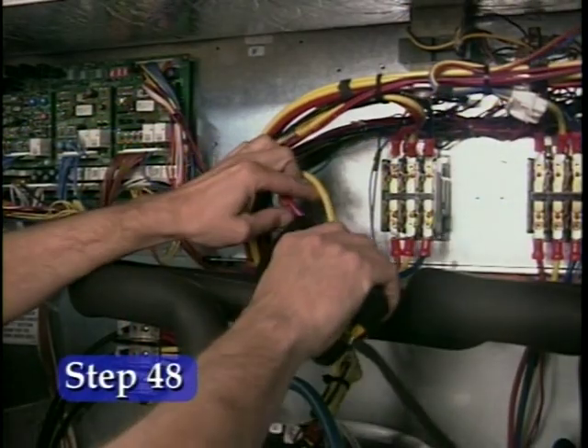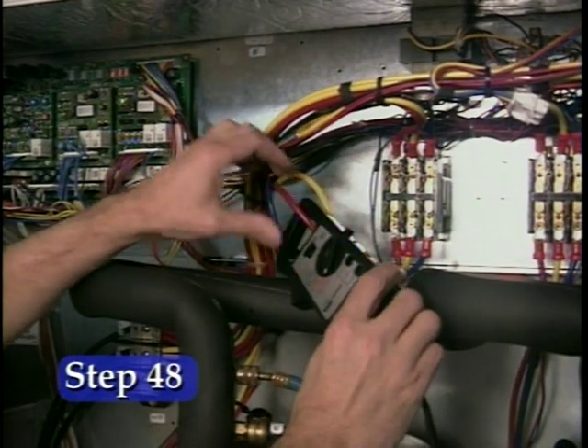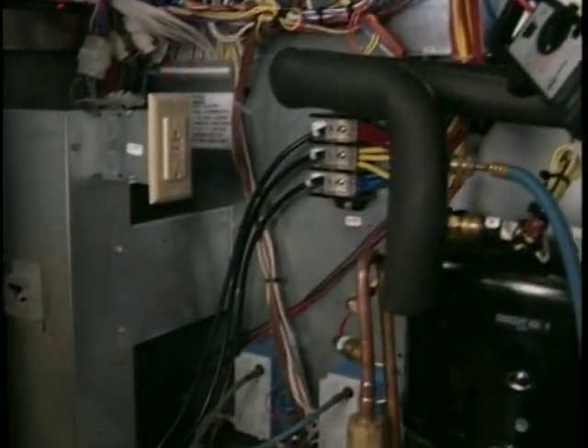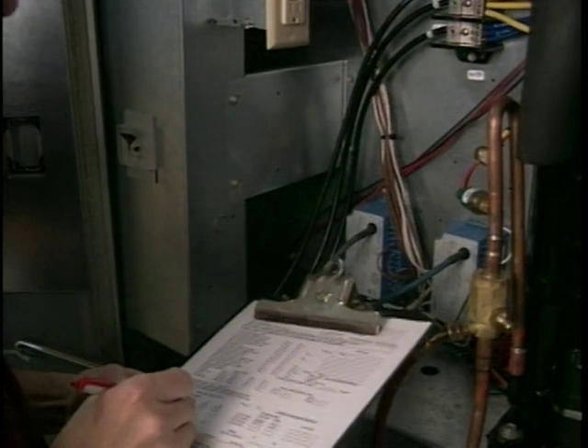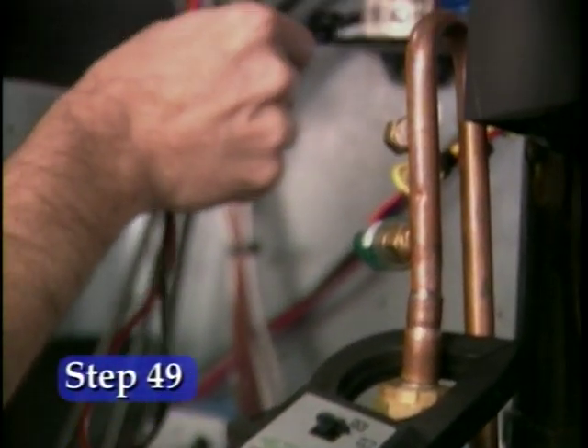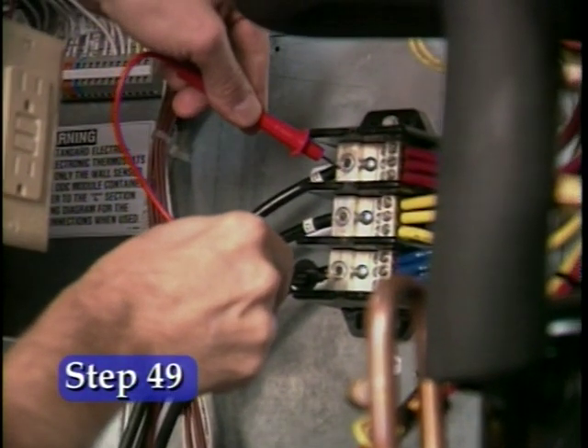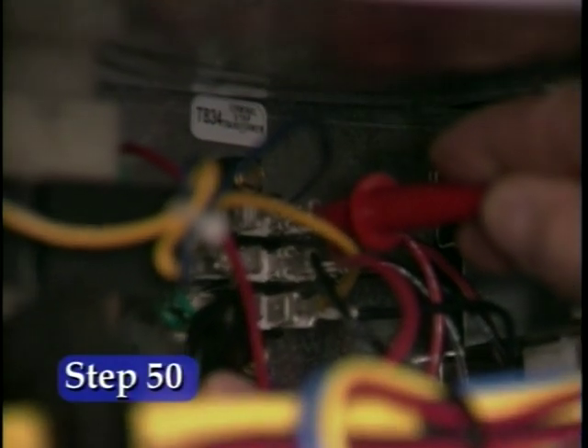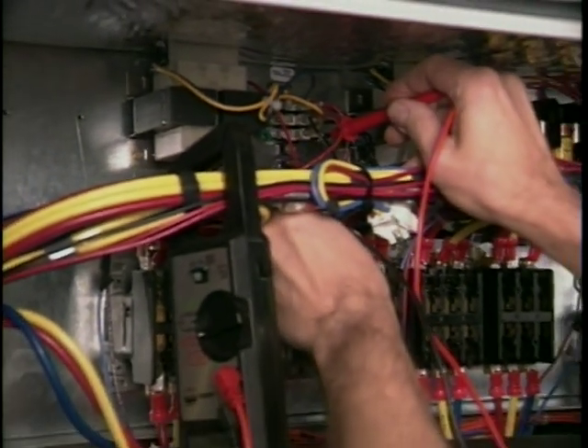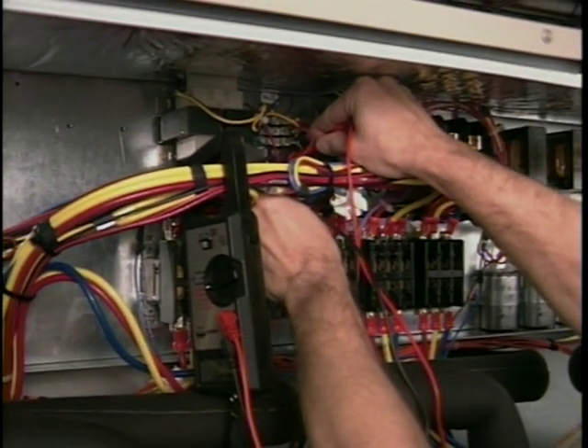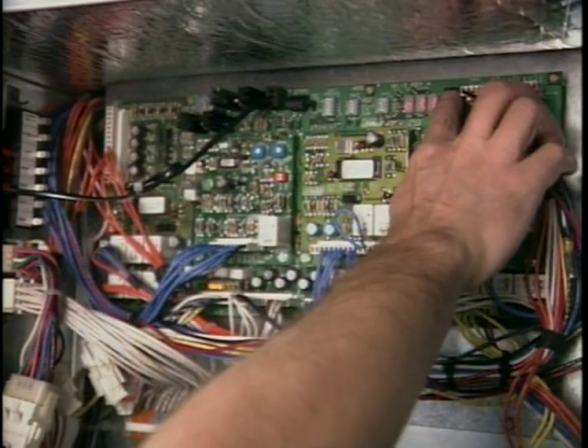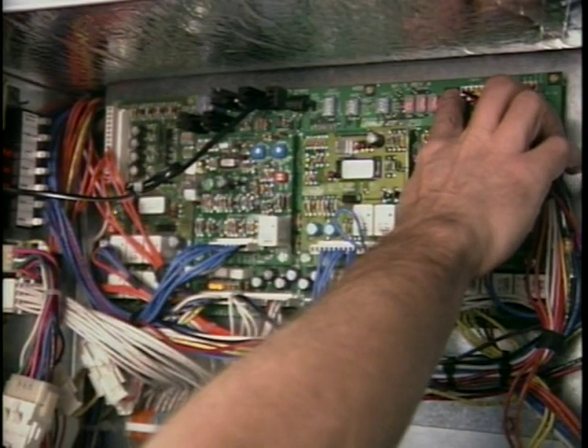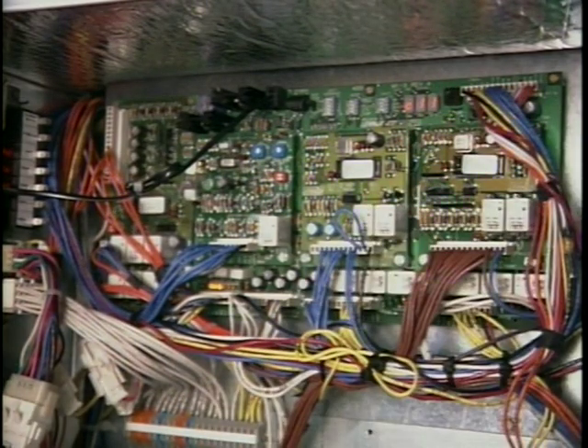Take amperage readings of indoor blower. Be sure the blower door is closed when taking these readings. Take voltage readings while the compressors are running. Take control voltage readings at TB34 for transformer T1 and at TB35 for transformer T18. Turn the compressors and fan off by pressing the display push button until the periods on the LED readout disappear.